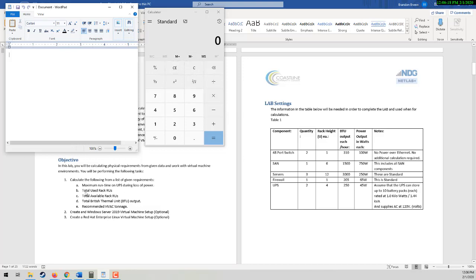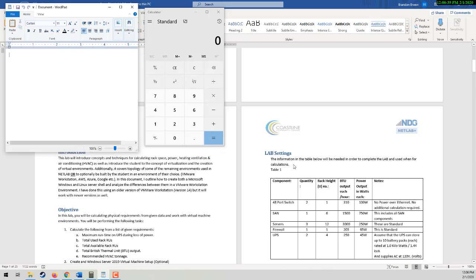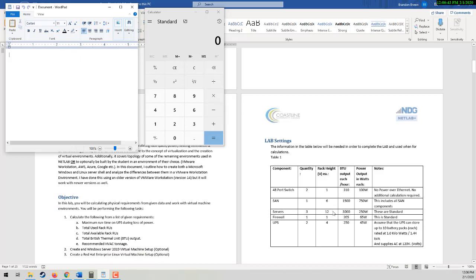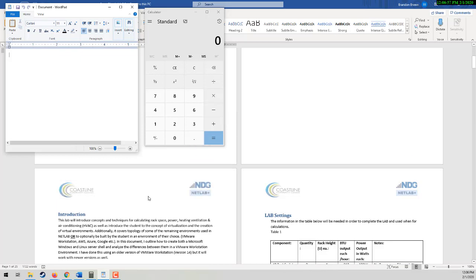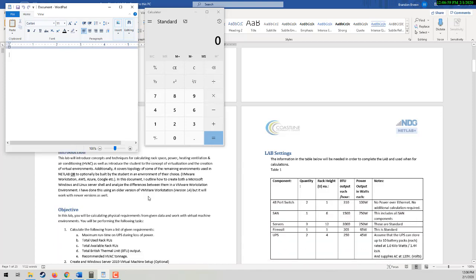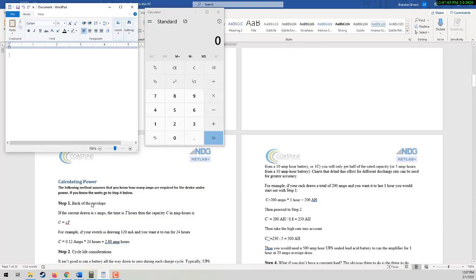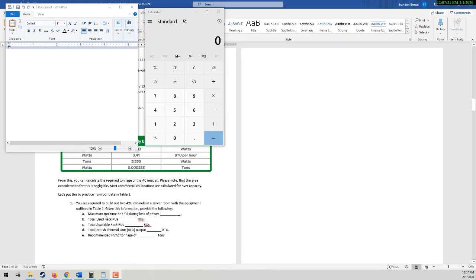Looking at the objectives, we need to calculate the maximum run time for the UPS, the total number of RUs, the available rack RUs, and the total BTU output and the recommended HVAC tonnage. With that in mind, you have the components that are going to go into your racks, the number, the quantity. In the explanation, I say that you're going to have two 42U racks at your disposal. So you're required to build out two 42U cabinets in the server room with the equipment.